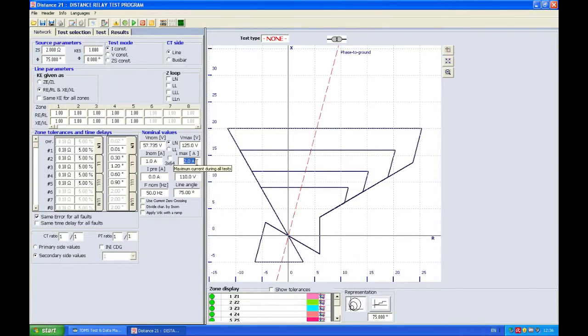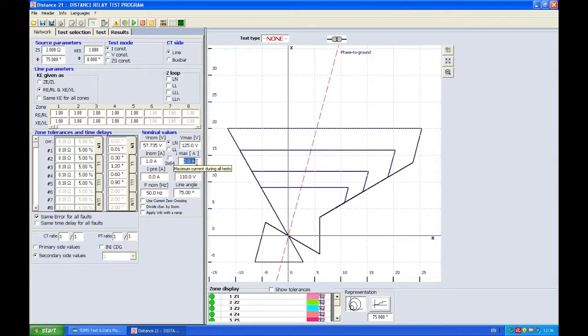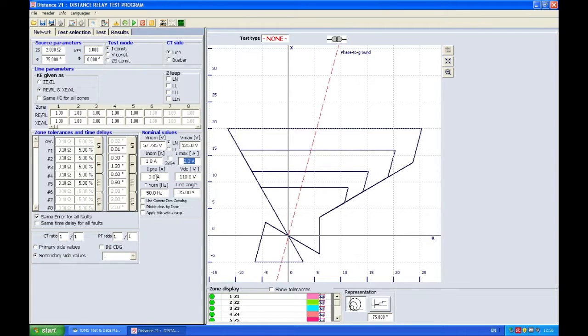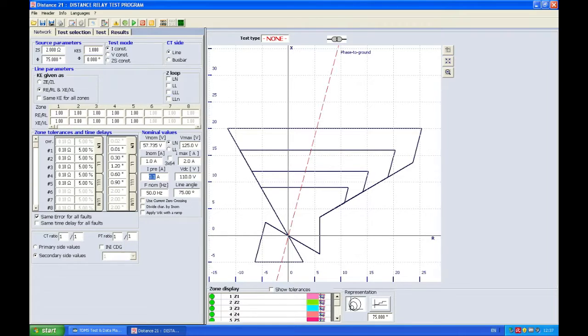Maximum current 2 amps. You can decide what is your maximum current if you don't want to go too much overboard in order to protect your current inputs. And if you want to generate a prefault with a certain current you can enter that current here, so for example 0.1.